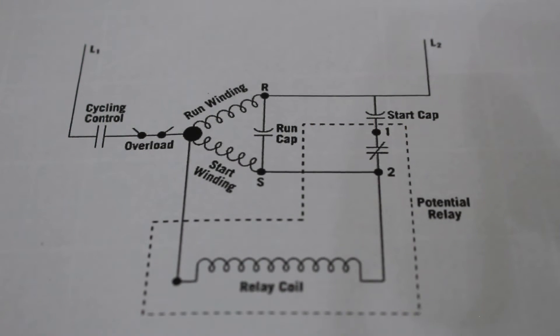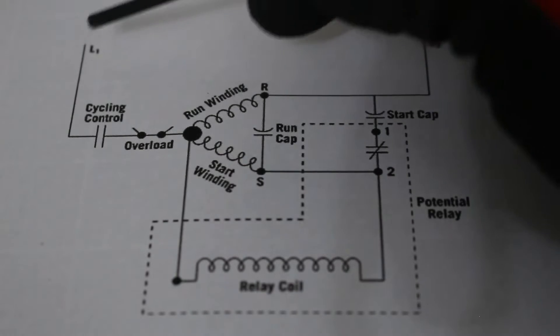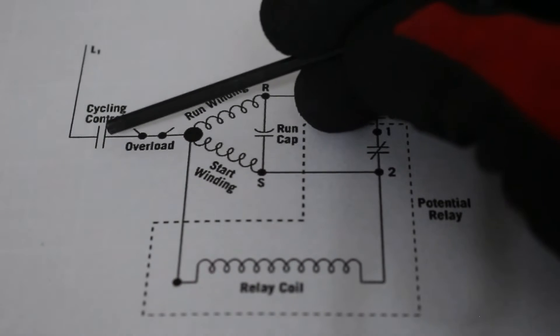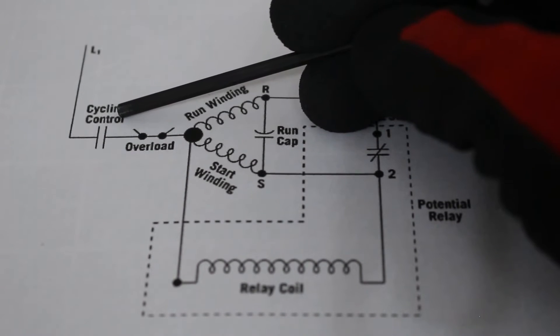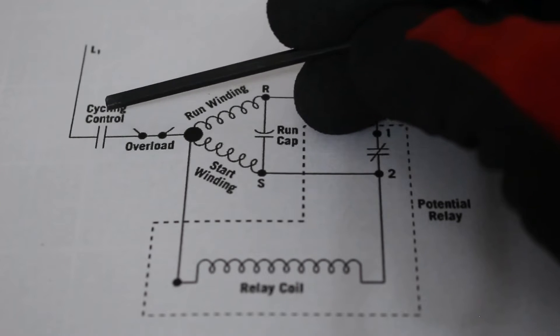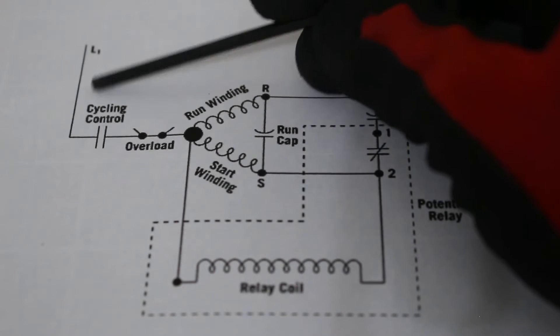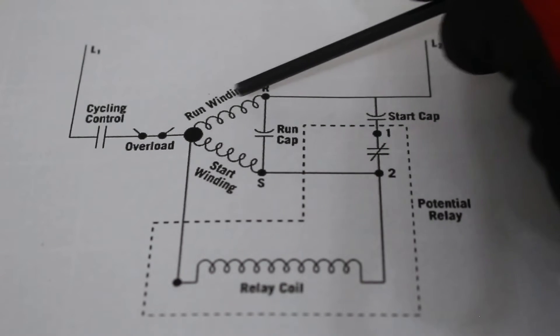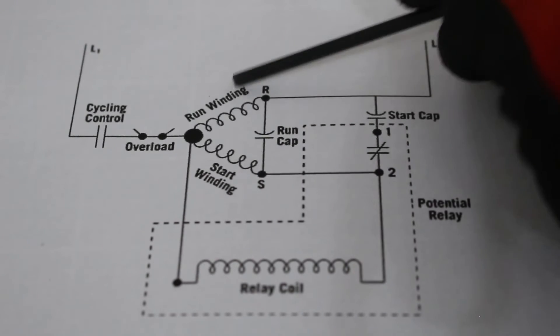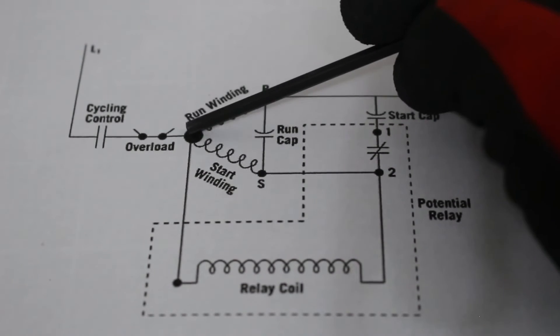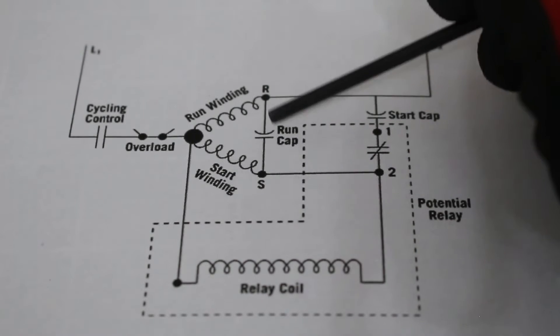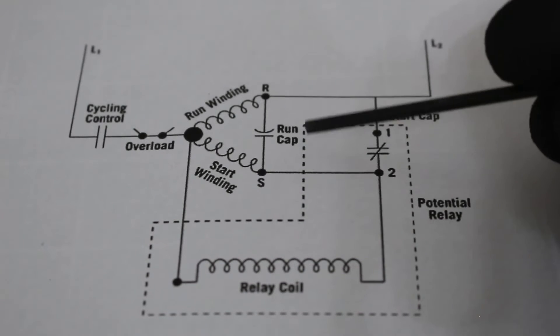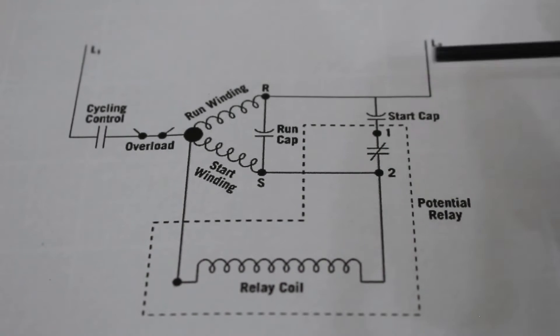Let's begin by going over exactly what we have here, and what we're looking at. Here is line 1 coming in, and here is line 2. Here we have normally open contacts, and it's going to be our cycling control. To keep things simple, let's just say this is our thermostat. Power comes in, goes into our overload, which is for our compressor. This right here is our compressor. This is our common point. Run winding, start winding. We have a run cap, and we have a start cap. In these dotted lines, this is our potential relay.